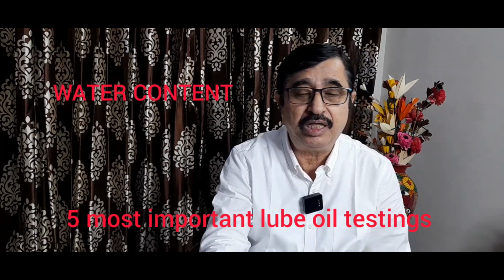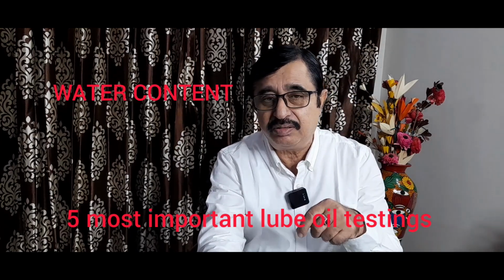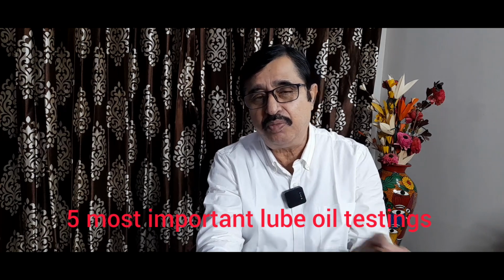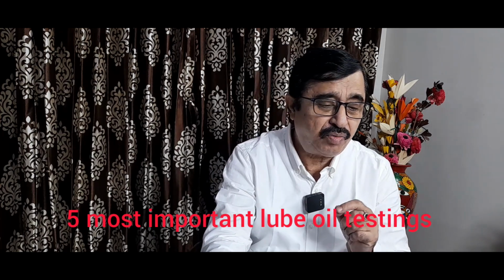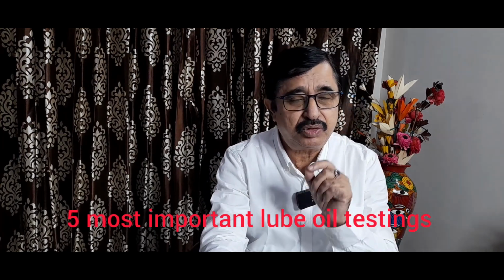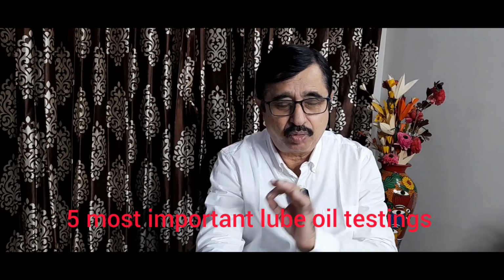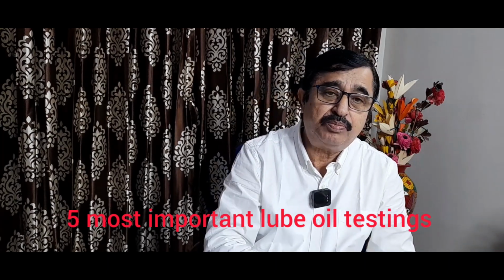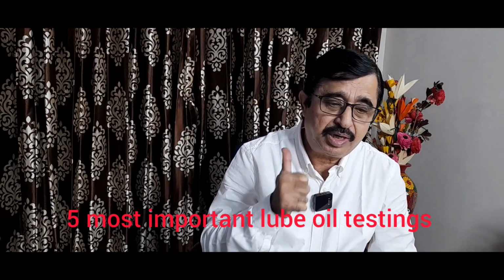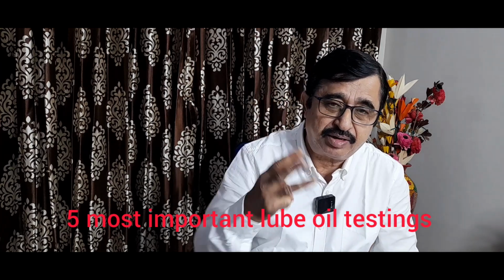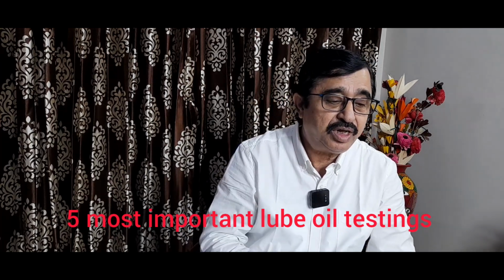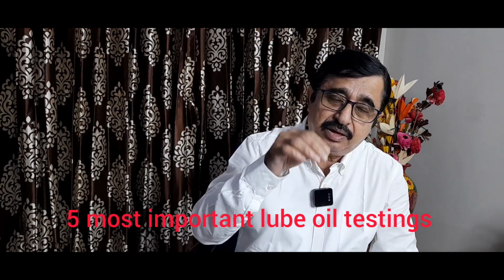It is very important. If water is mixed in the oil, it will be emulsified, and the oil's properties will slowly be lost in the course of time. Water contamination promotes degradation, chemical corrosion and bearing fatigue. These 3 things it promotes. And water in a turbine is a top concern.